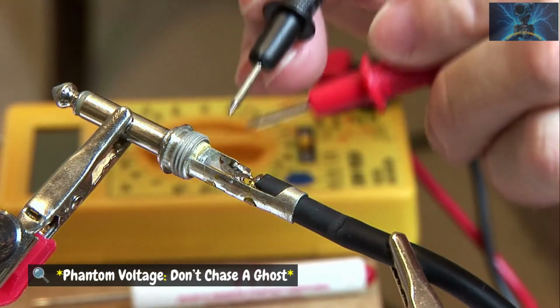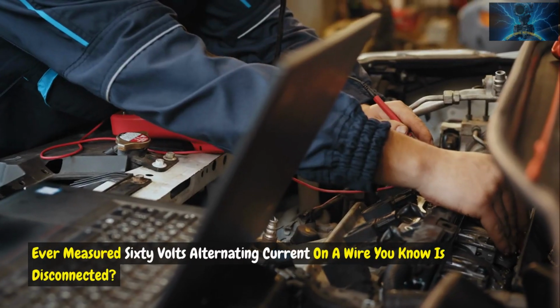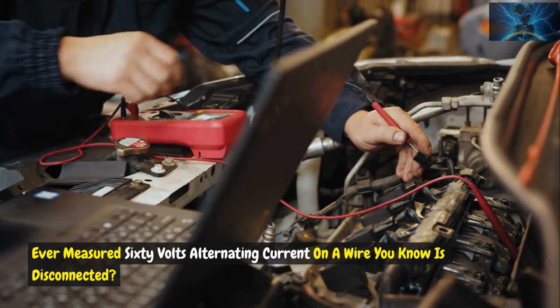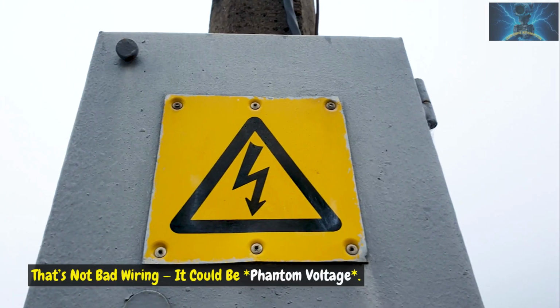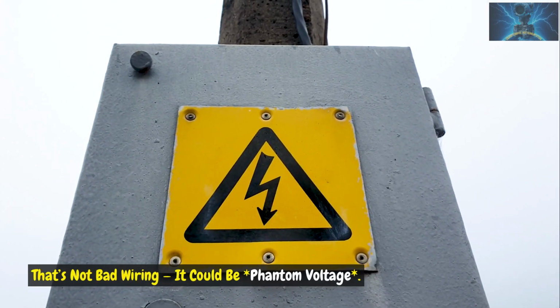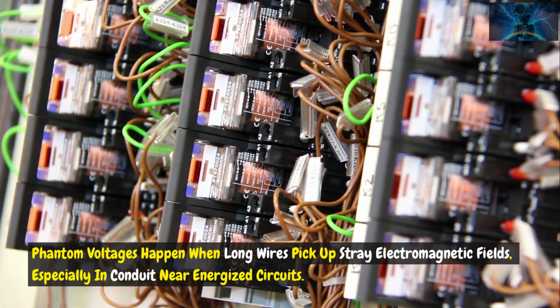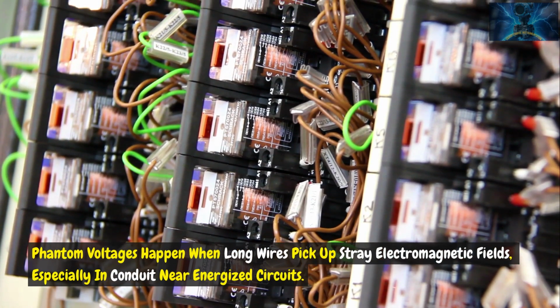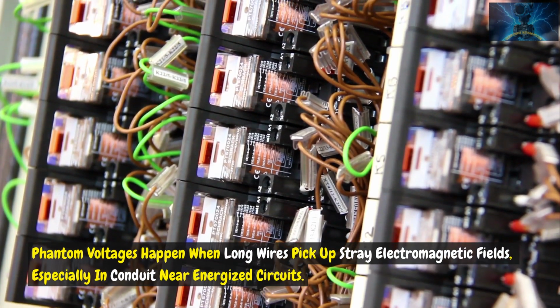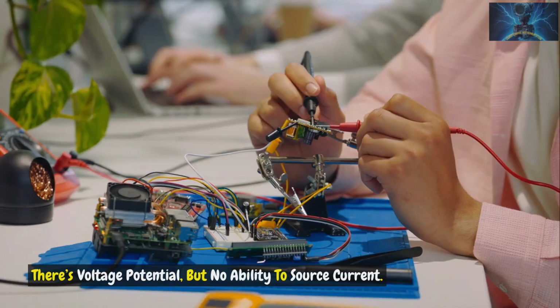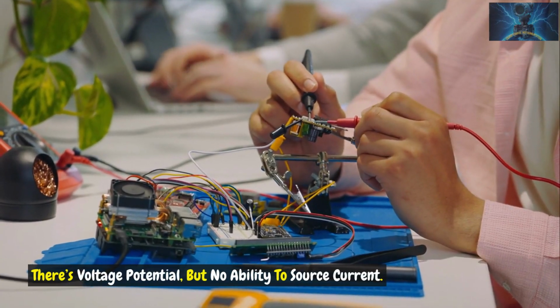Phantom voltage: don't chase a ghost. Ever measured 60 volts alternating current on a wire you know is disconnected? That's not bad wiring. It could be phantom voltage. Phantom voltages happen when long wires pick up stray electromagnetic fields, especially in conduit near energized circuits. There's voltage potential, but no ability to source current.